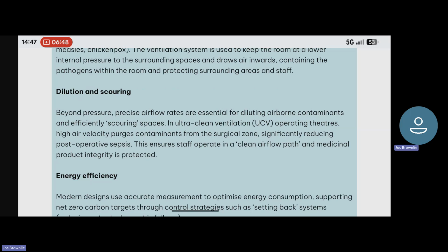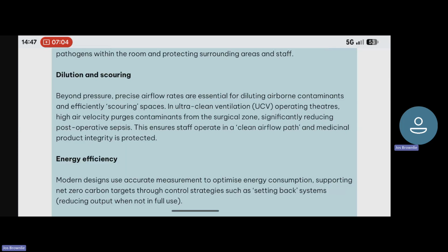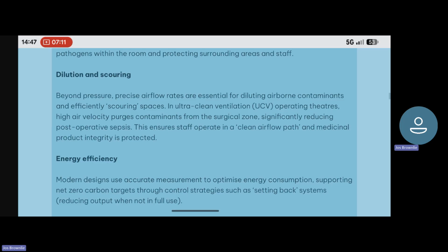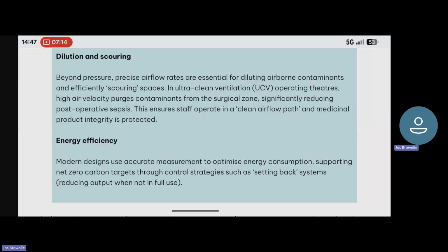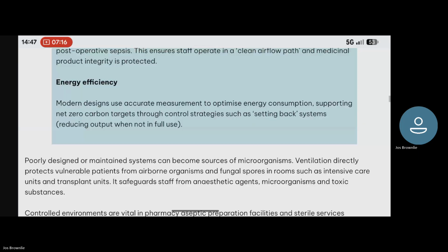Dilution and scouring. Beyond pressure, precise airflow rates are essential for diluting airborne contaminants and efficiently scouring spaces. In ultra-clean ventilation or UCV operating theatres, high air velocity purges contaminants from the surgical zone, significantly reducing post-operative sepsis. This ensures staff operate in a clean airflow path and medicinal product integrity is protected.